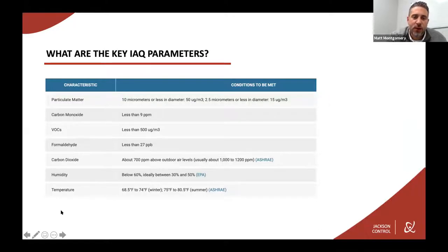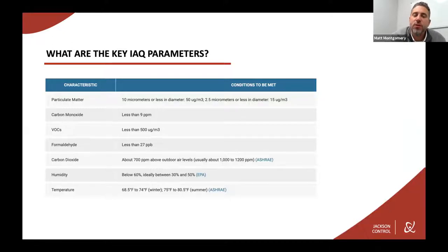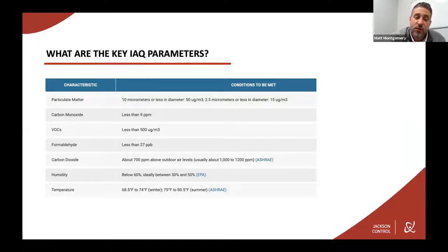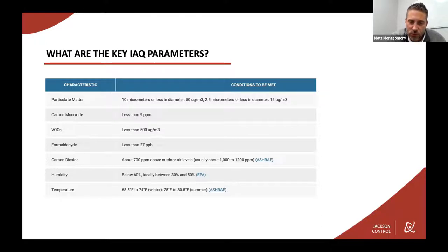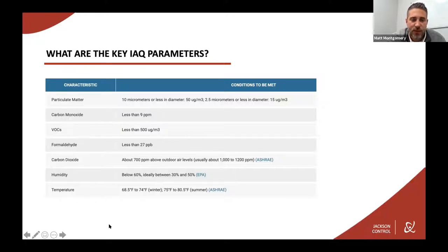What are the key parameters of indoor air quality? Particulate matter is defined by size — PM10 is 10 micrometers or less, PM2.5 is 2.5 micrometers or less. Carbon monoxide should be less than nine parts per million. VOCs, less than 500 micrograms per cubic meter of air. Formaldehyde, less than 27 parts per billion. Carbon dioxide, about 700 parts per million above outdoor air levels, usually about 1,000 to 1,200 parts per million. Humidity, ideally between 30 and 50 percent. And temperature, 68.5 to 74°F in winter and 75 to 80.5°F in summer.